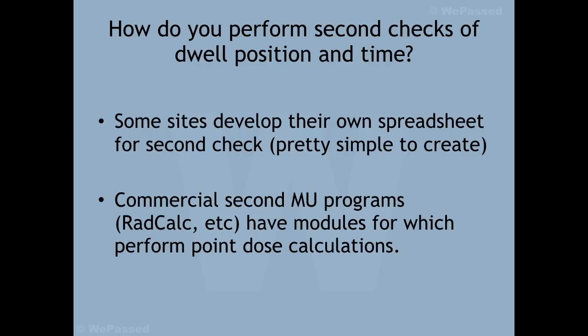You just use the data from your planning system, because if the planning starts the wrong way, everything's wrong. You need to check the prescription submitted by the doctor and the parameters written in it — the cylinder diameter, how many cylinders or domes used, the treatment length given by the doctor, and the point at which the doctor prescribed the dose, whether surface, 5 millimeters, or some other point, or whether the doctor wants to treat the volume or another part. The secondary check is really necessary. First the plan must be done the right way, then you need to check the time or dose is correct. That's one good question.